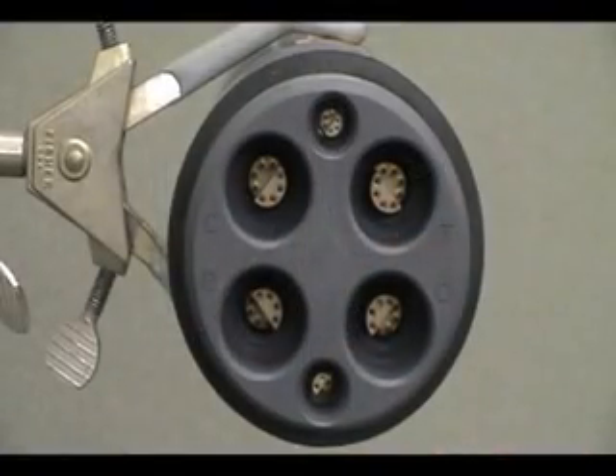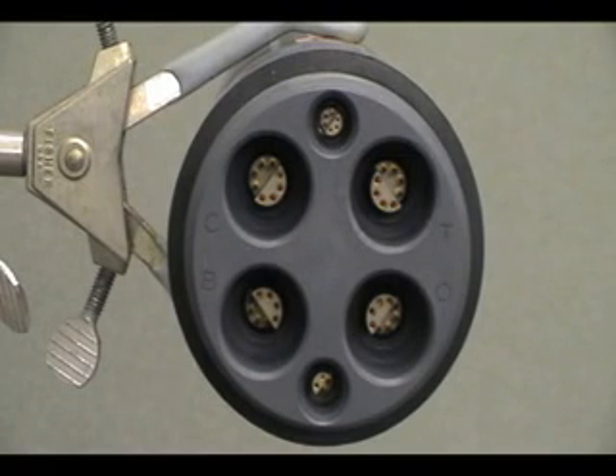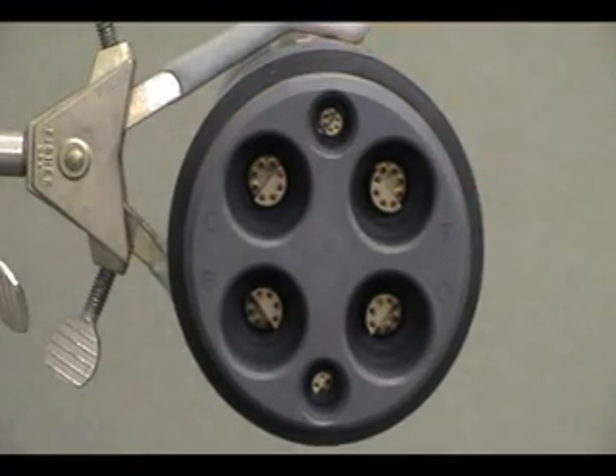Step 2. Installing sensors. This sonde has two different types of ports capable of accepting sensors. The first type are called optical ports. There are 4 optical ports on this sonde, labeled O, B, C, and T. O port is for the optical dissolved oxygen sensor, model 6150. C port is for the optical chlorophyll sensor, model 6136. T is for the optical turbidity sensor, model 6025. B port currently has no optical sensor, so it is blank for now.